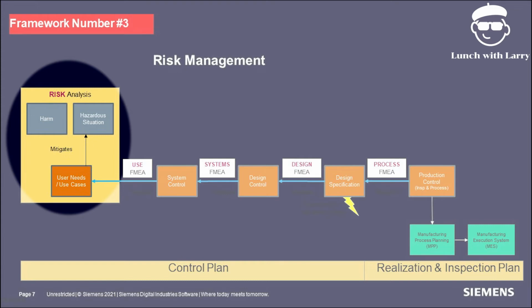So I'm going to have a harm that's infection, and the hazardous situation is that the device introduces harmful bacteria to the patient. So that is the hazardous situation that causes the harm of infection. Now we're going to have a mitigation that is the user need, and the user need is that the device be sterile. So this is our example at the 14971 level, and we believe if we present devices that are sterile, what's going to happen is that hazardous situation, that the patient will be infected with the device, will be mitigated. And so the user need then is very important to assuring that we have control of the occurrence of that hazardous situation.